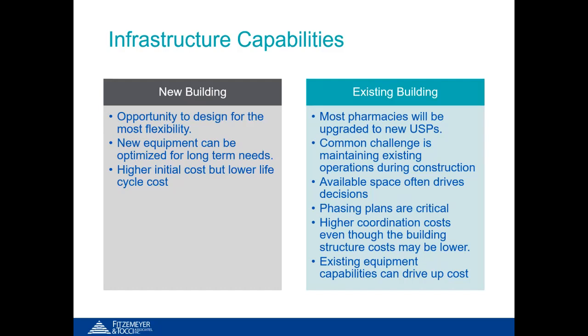The methods for dealing with this type of upgrade are to either incorporate areas around the existing pharmacy into the new pharmacy footprint, or construct a new pharmacy in an alternate location to ensure the existing pharmacy remains operational at all times. Both options are restricted by the amount of available space within the existing hospital, and the decision between the two is typically driven by where and what space is available.